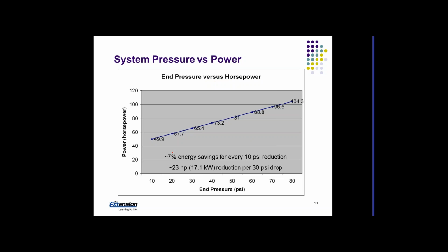So in Wisconsin, our average water pumping depth is probably about 90 to 100 feet. Central Sand, it's much lower than that, but just on a general average. So we can save about 7% energy costs for every 10 psi of reduction. Or if we did a 30 psi reduction, so we went from 80, say, down to 50, we'd save about 23 horsepower or 17 kilowatt of power requirement to drive that pump.